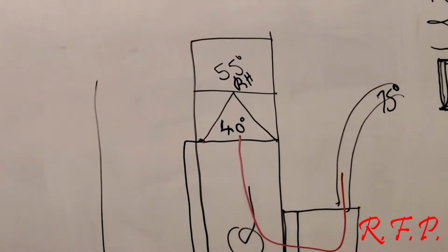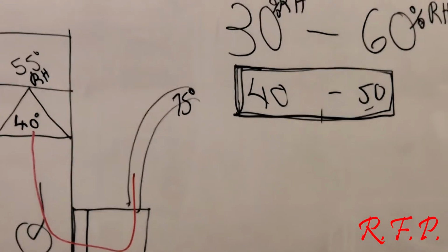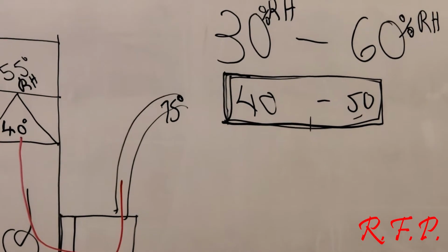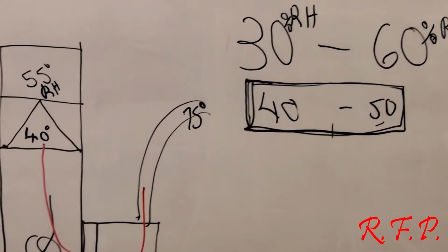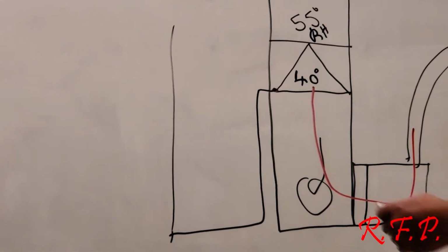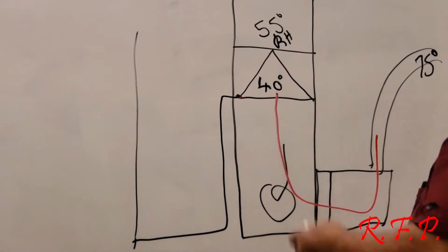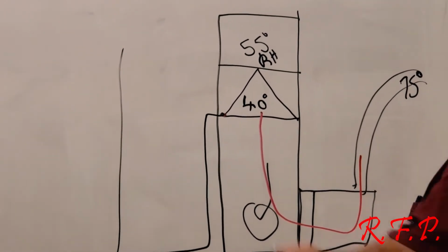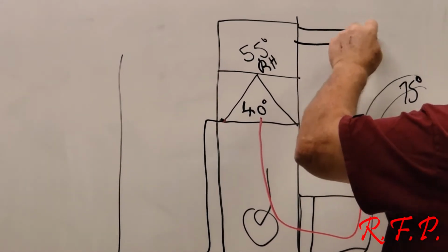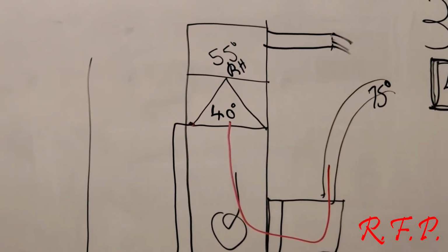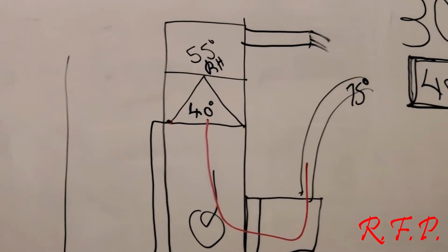Why? Because that air is at 55 degrees. What did we say the dew point was? 50 degrees, or 56 degrees. So this air is gonna be at 80% humidity if you measured it above the plenum. But when it gets out into the room and disperses again, the room humidity drops overall because you took moisture out of the air.